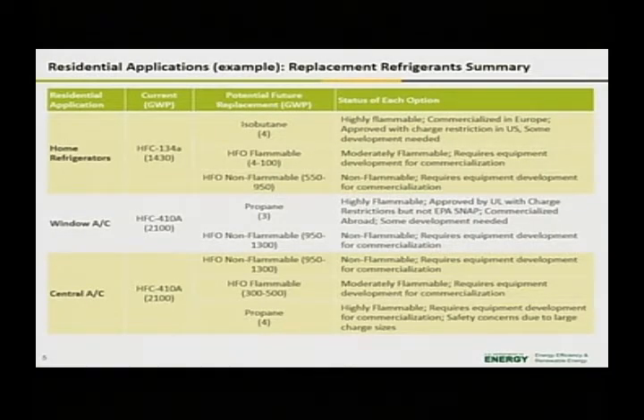And if you look at potential future low GWP refrigerants, these candidate blends or different refrigerants, you'll see one thing that a lot of them have. Yes, they are going lower in global warming potential, but they have some trade-offs. The major trade-off is that a lot of them are flammable. So there's a price to pay. And a lot of these would also entail a lot of R&D to be drop-in replacements, so they're not the easiest to implement. And their safety, like I said, the flammability.